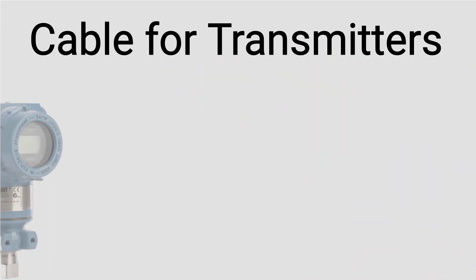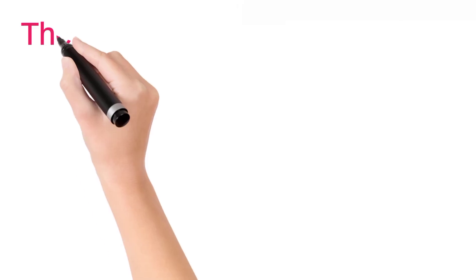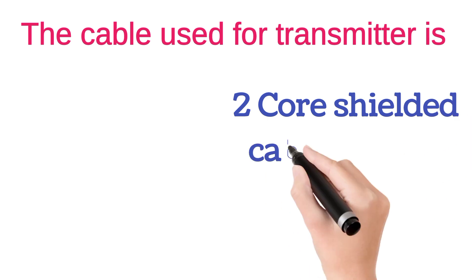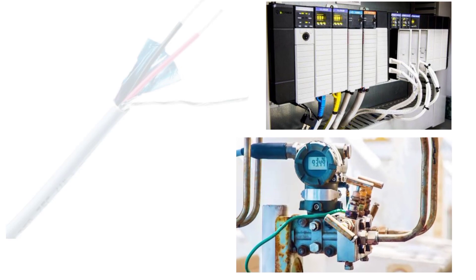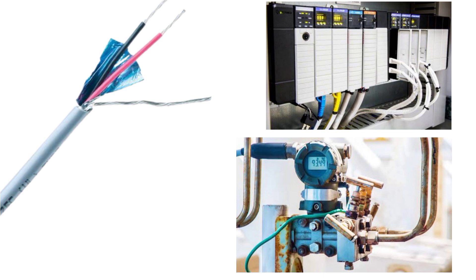Now we will see the cable for transmitters. The cable used for pressure transmitters, level transmitters, and some other transmitters is a 2-core shielded cable, also known as a pair cable. Between the PLC and transmitter, a pair cable is used — one wire is connected on the positive terminal and the other on the negative terminal. The shield connection is optional; we can connect it or cut it.